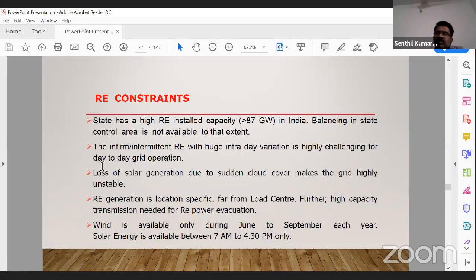In case of loss of generation, such as when more clouds appear, there's huge variation in solar generation - except during a solar eclipse, where the loss variation is about 12,000 megawatts. As per preliminary calculation, 12,000 megawatts was expected and 11,943 megawatts was actually reached - that huge variation. Sudden variation based on cloud cover makes the grid highly unstable. At that time, we immediately balance the solar demand by increasing hydro generation and gas station and conventional power, and stabilize the grid within a shorter duration.